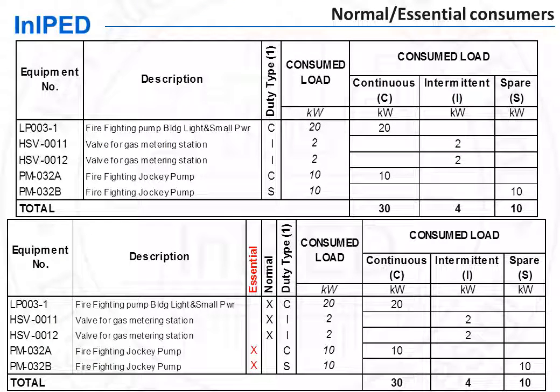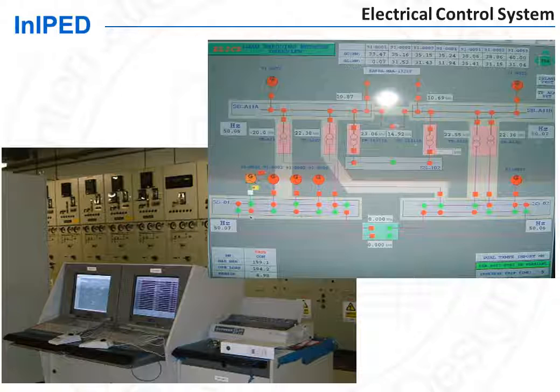The identification of essential consumers is done by the electrical engineer by asking process and mechanical engineers. A load shedding system is implemented so that in case of loss of the main power generators, the limited amount of essential power available from the emergency generators is fed to the essential consumers only. This load shedding, together with other functions of monitoring and control of the electrical system, is performed in the electrical control system, also called the power distribution control system, PDCS.